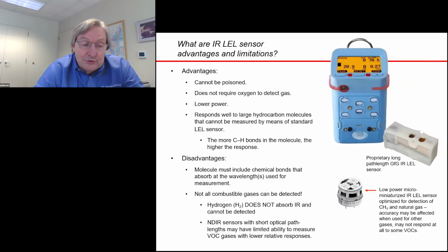Advantages of infrared LEL sensors are they can't be poisoned. They don't require oxygen to detect gas. As I mentioned, they use less power. They respond really well to large molecules. The more carbon hydrogen bonds in the molecule, the higher the response. So you actually get a larger signal from, say, a hexane molecule where you have 6 carbons in the molecule, and a higher response than you have with a methane molecule where you have 1 carbon and 4 hydrogens in the molecule. Disadvantages are the molecules have to be able to absorb infrared light.